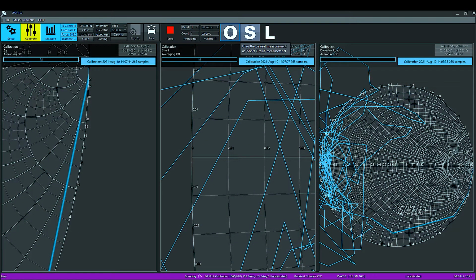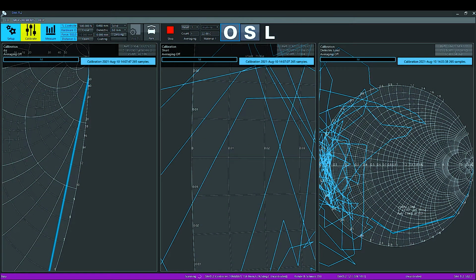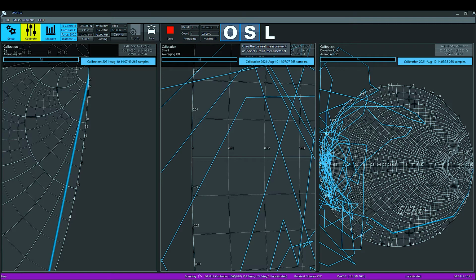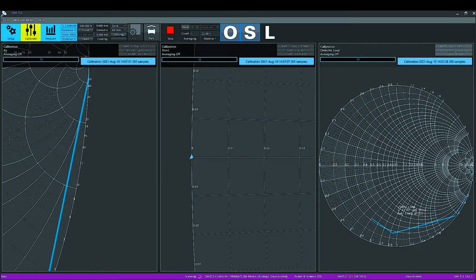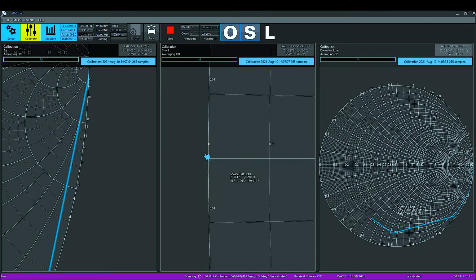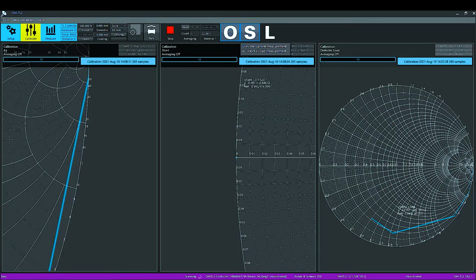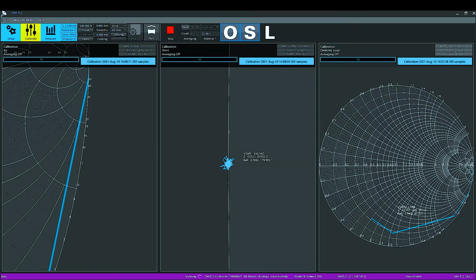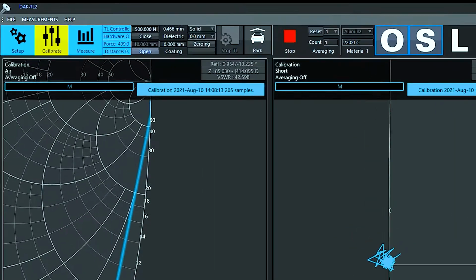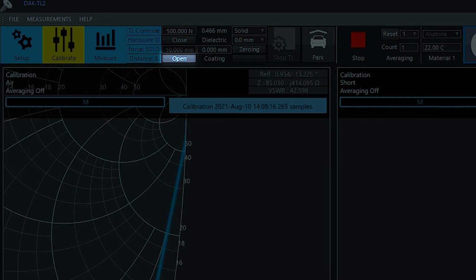When the trace on the Smith chart stabilizes towards the short point, I click the S calibration button in the GUI. To improve the quality of the short, I twist the tape under the probe. If I get a better short, I press the S button again. After short calibration, I press the Open button in the base system controller.